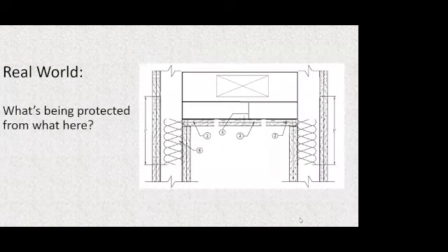Okay. Here's another common misconception in the drywall world, that we have corridor designs that are used for enclosure of the duct system. This is a lay-in ceiling. This is not a lay-in ceiling. This is a false ceiling, right? And it looks like an H design, but if you look very, very closely, they don't have the shaft liner protecting the duct area to the exit passageway. What are we protecting here? In this case, we're protecting the duct from the exit passageway, but we're not protecting the exit passageway from what's above the ceiling. I think we missed something.